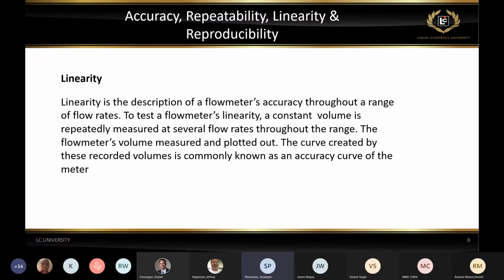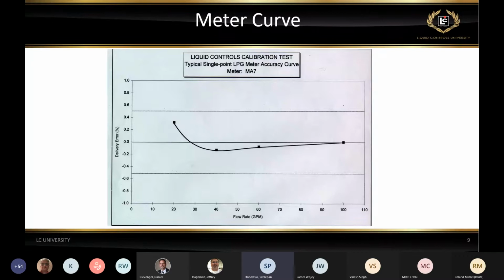If we test the meter throughout the range of flow at the different flow rates, different points, we'll be able to plot those points and create what's called a meter curve. That's an example of a meter curve, an MA7 meter tested between 20 to 100 gallons a minute. And that's a typical meter curve of a Liquid Controls meter. Calibrated at 100 gallons a minute, that's where the meter is zeroed out. That has its most accurate point, and then it's tested at the different points, and those points are plotted to represent the curve of that meter.